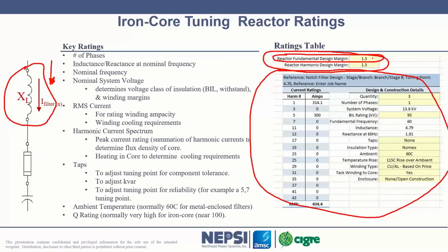But if you knew what the reactor suppliers were doing, they're building a custom wound device. It's not something that is used over and over again. They don't know the cooling capacity within the enclosure system that you're supplying, and therefore their design and analysis tools that they use to develop the iron core reactor might not be conservative enough. So by putting this in there, it's helping to guarantee that the filter reactor that you have is correct. It's also helping to guarantee that you will not ever enter into a saturation condition, trying to avoid saturation.